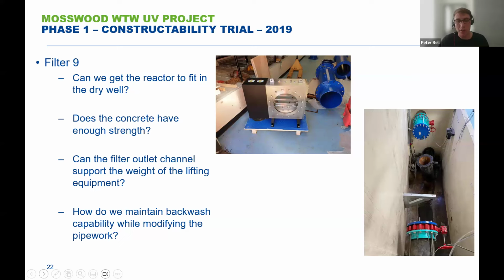At the time, we identified that Filter 9 was a really good opportunity to get in and do a trial of this equipment and validate all of our thoughts from the design process. Filter 9 was out of service at the time for a media change, which is a routine task that we go through every so often, depending on the filter media life cycle. So it presented a good opportunity to trial this without causing any further impact to the site. So the first question to ask ourselves is, can we actually get the reactor to fit within the dry well?